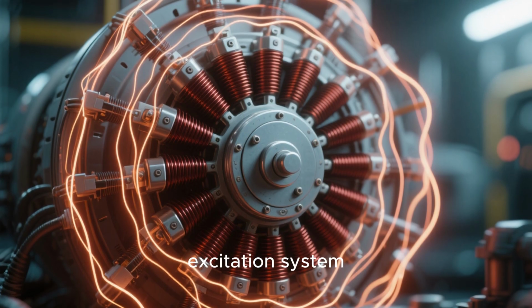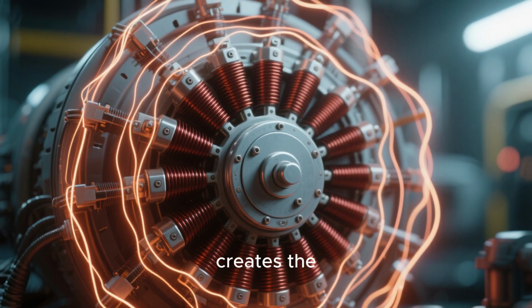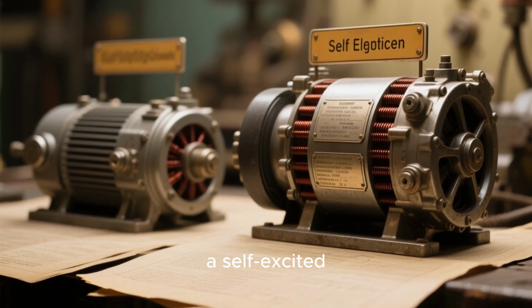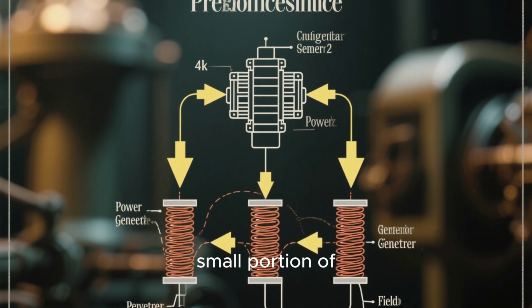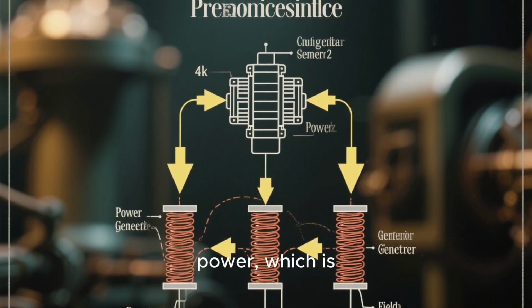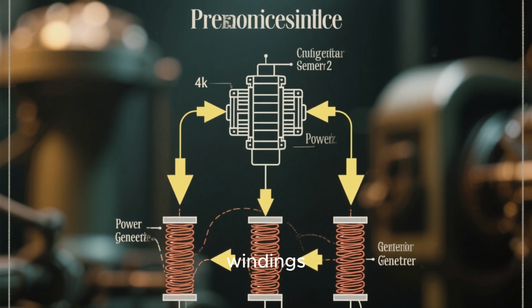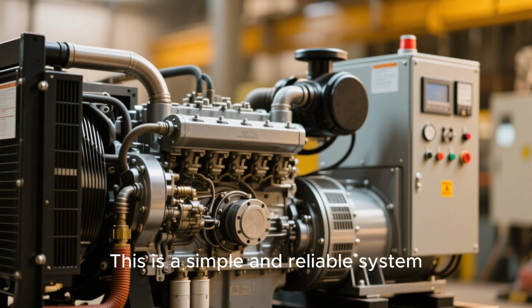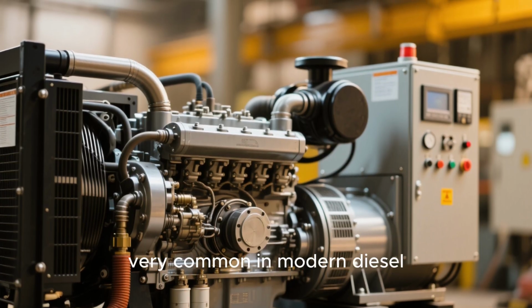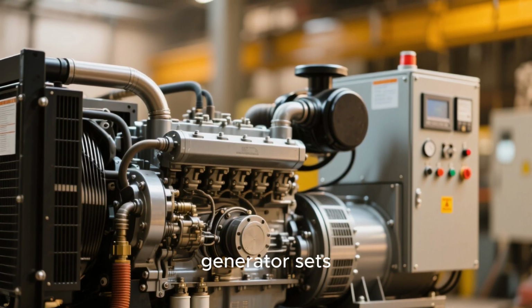We mentioned the excitation system earlier, which creates the magnetic field. There are 2 main types. The first is a self-excited generator. In this design, the generator uses a small portion of its own output power, which is rectified to DC, to energize its field windings. This is a simple and reliable system, which is why it's very common in modern diesel generator sets.